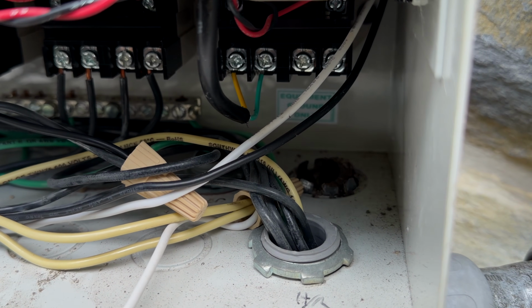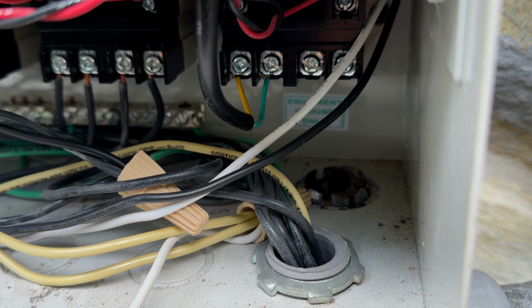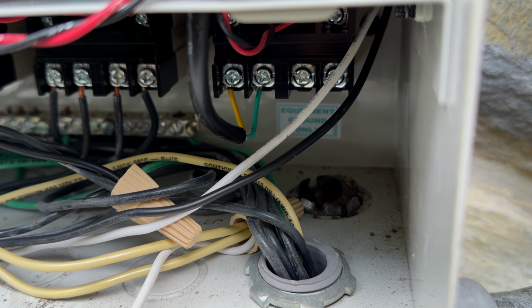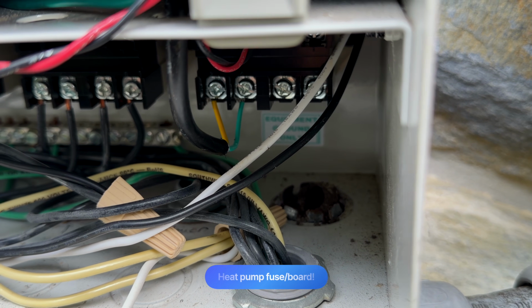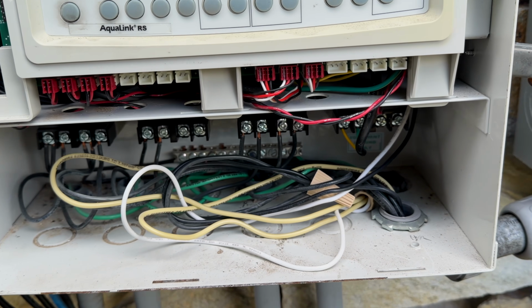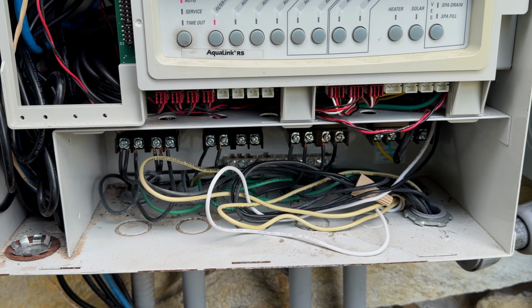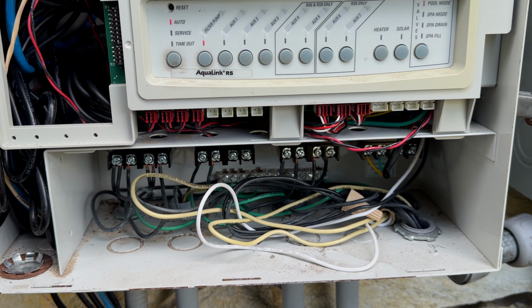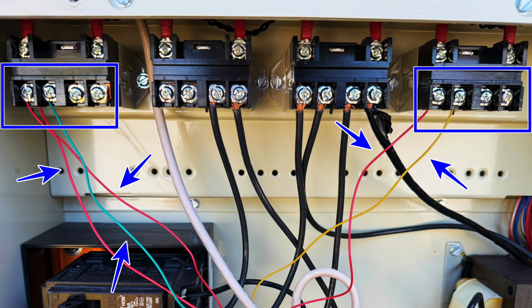Never, ever, ever mix high voltage and low voltage together on that relay. You will absolutely destroy, at best, just the fuse on the board, or at worst, destroy the board completely. I know it's been beaten into our heads to never mix high and low voltage together in the same area, but this is no different than when Pentair, back in the day, when their Superflows were starting to be able to work with the EasyTouch.